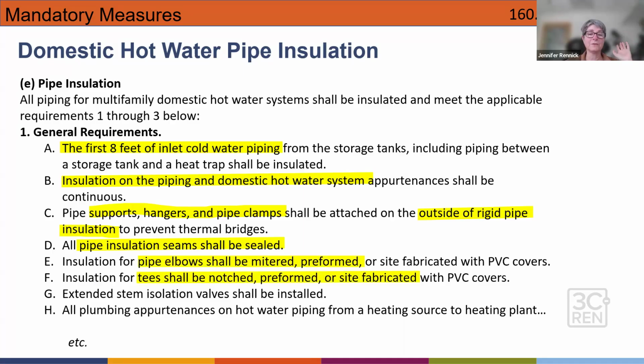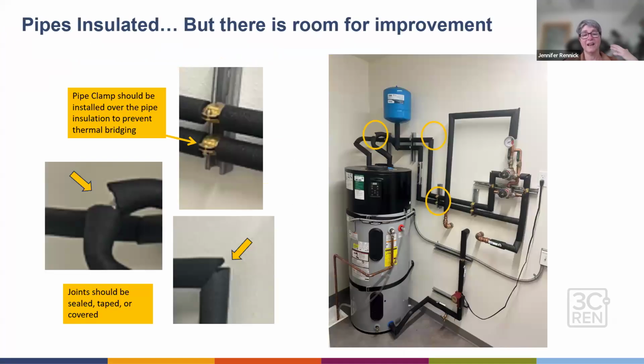that the pipe elbows and the T's need to be mitered, or preformed, or site fabricated with PVC covers, and that even the isolation valves need to have extended stems to allow the insulation around. And then it keeps going from here. This is just an excerpt. And the reason this is now under mandatory measures so explicitly for multifamily projects is because we've seen, and the CEC continues to see, that for these heat pump water heaters, yes, a lot of the pipes are insulated, but there's a lot of room for improvement.